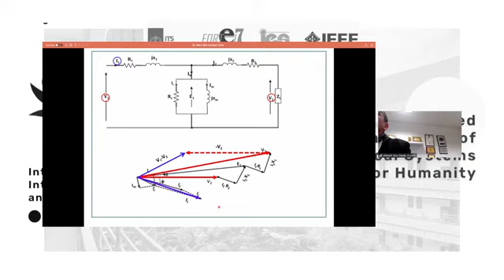So my thought was, can I use this ellipse as the fingerprint for each phase? And if I have any deviation from this, either a bigger area or a rotated ellipse, can that be an indication of a fault? So that's a graphical illustration of the technique, very simple. All I want to do is to measure the difference of the voltage against the input current. So for each cycle like that, I will detect the current and voltage and plot the ellipse in 20 milliseconds.